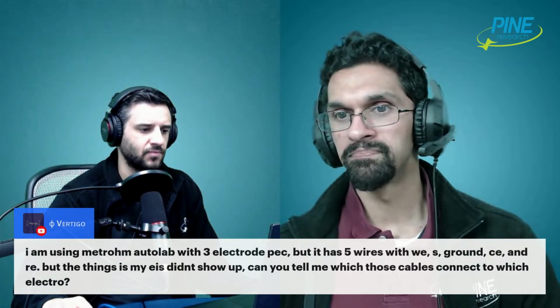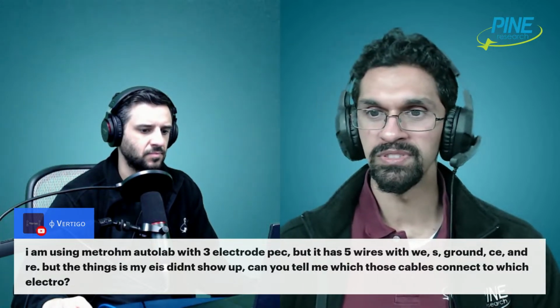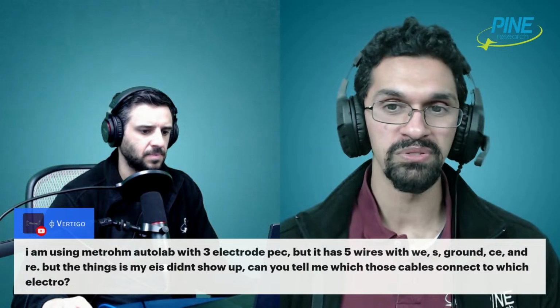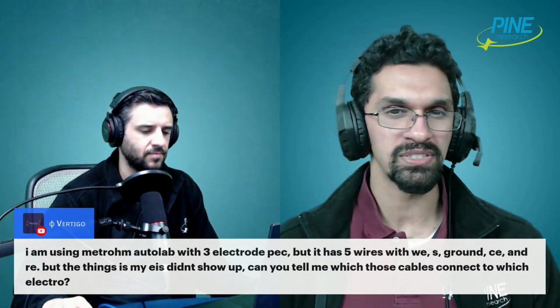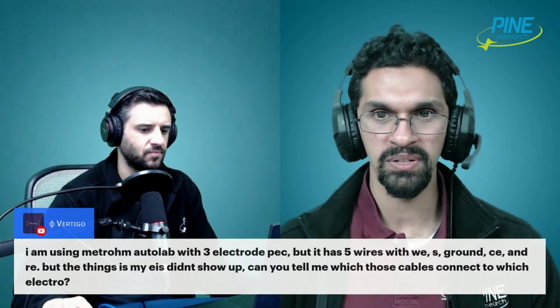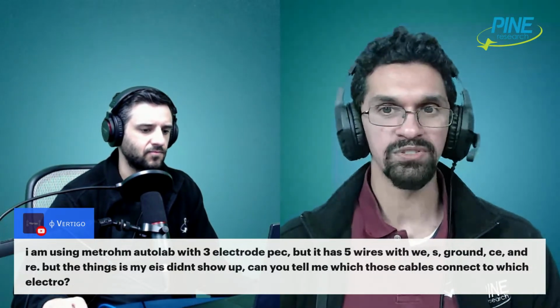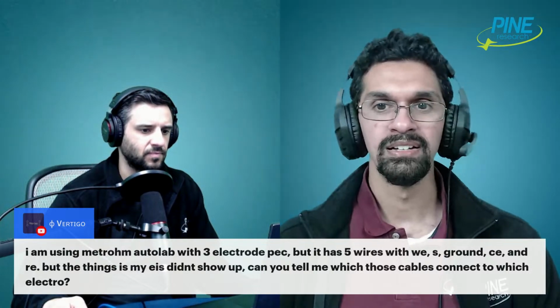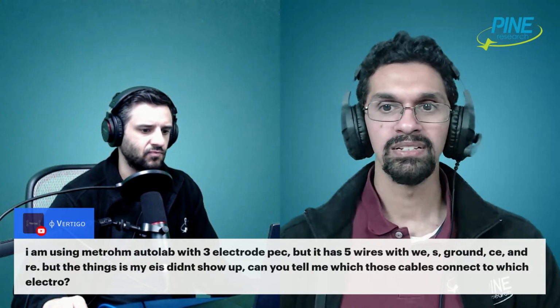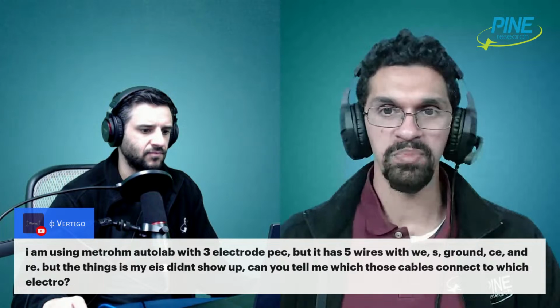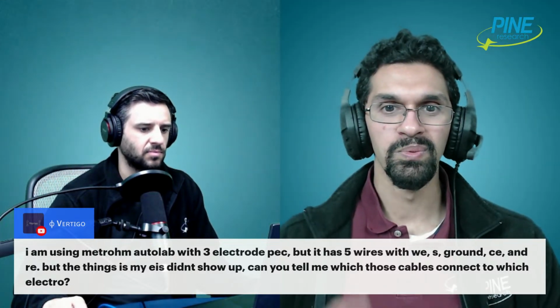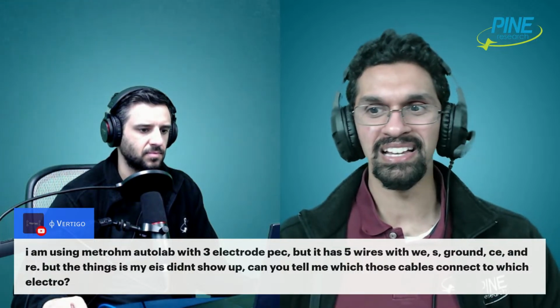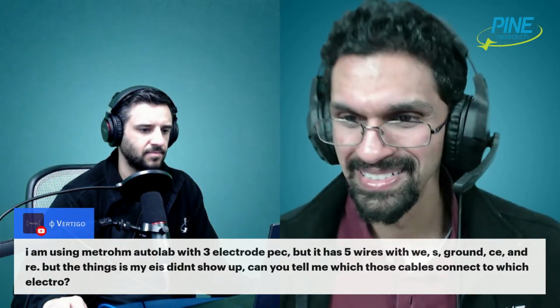And Uma had a comment for you, which was if you were doing a 2-electrode system, you would need to short the counter to the reference. But it doesn't sound like you have a 2-electrode system. With a 3-electrode system, your working and sense lines need to be connected, but the counter and reference are separate, going to their respective electrodes. So try that, and then I think the EIS should show up.